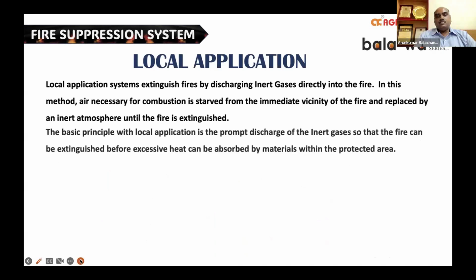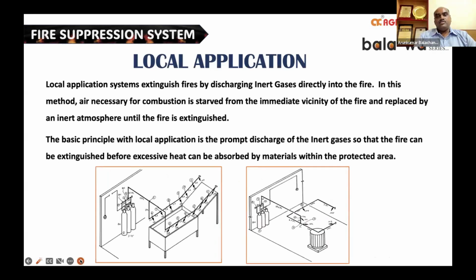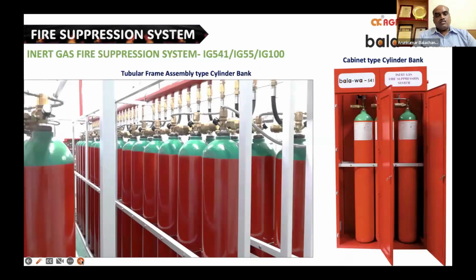Local application comes in where, for example, in a very big area, we have just a small server cabinet or a switching equipment cabinet. In order to protect this particular cabinet, we cannot go for complete room protection. So we can go for localized protection of just the cabinet or the area around the cabinets or switching equipment. Here, we concentrate on the vicinity of the cabinet, bring down the oxygen content to less than 15%, and also give additional extended discharge so that external oxygen does not rush into the fire to feed it. Here are some pictures of how an inert system looks.